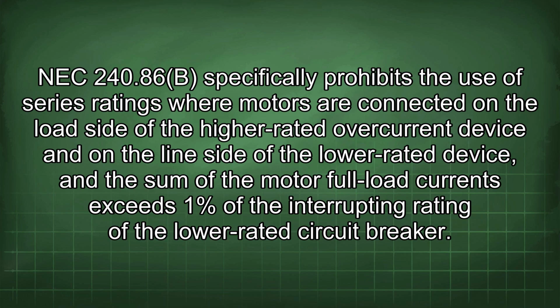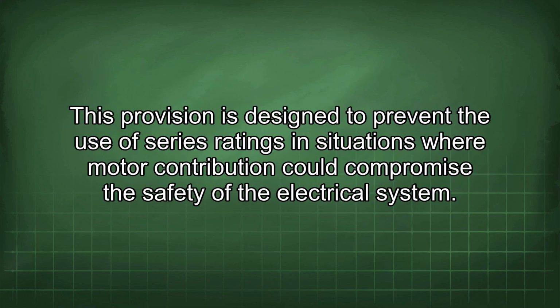NEC 240.86(B) specifically prohibits the use of series ratings where motors are connected on the load side of the higher rated overcurrent device and on the line side of the lower rated device, and the sum of the motor full load currents exceeds 1% of the interrupting rating of the lower rated circuit breaker.